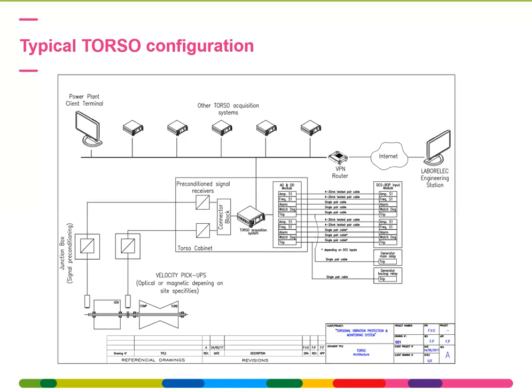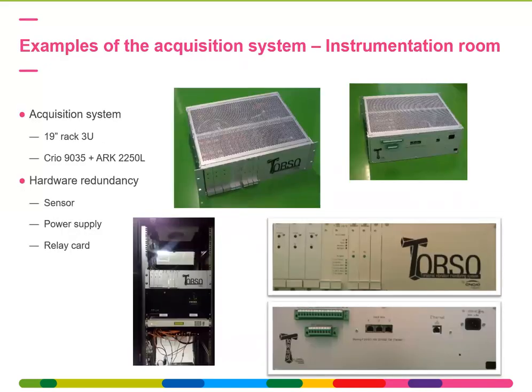So now we are going to explain the different components of this overview, mainly the junction boxes nearby the machine room and the torso rack itself, where all the acquisition and post-processing is done. So here you can see the torso rack. It's a 19-inch standard rack, which can be put in any cabinet, and holds a compact RIO and a computer to store all the data that is being developed by the system. The hardware redundancy, as explained already, is important. This is on the sensor level and also on the different components level, so the power supply and the relay cards.